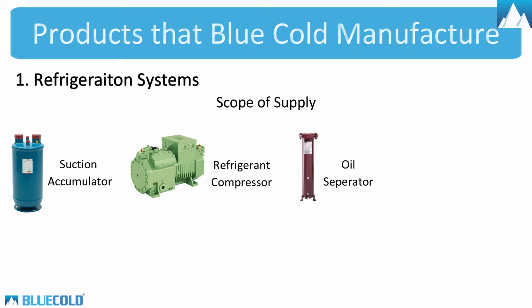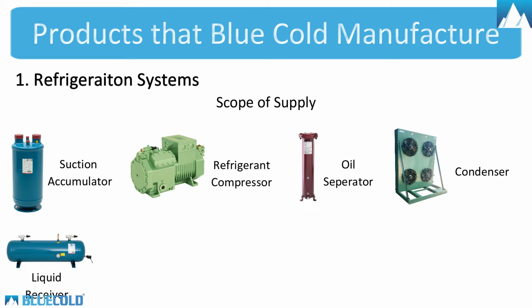Oil separator. It is installed in between the compressor and condenser. Its main function is to separate the refrigerant and oil, which came from the compressor, and send only compressed refrigerant to the condenser and oil back to the compressor. Condenser. The temperature of the refrigerant goes high when it gets compressed. A condenser brings down its temperature with the help of air or water. Liquid receiver. This vessel contains refrigerant coming from the condenser and ensures to pass only liquid from the refrigerant to the heat exchanger.